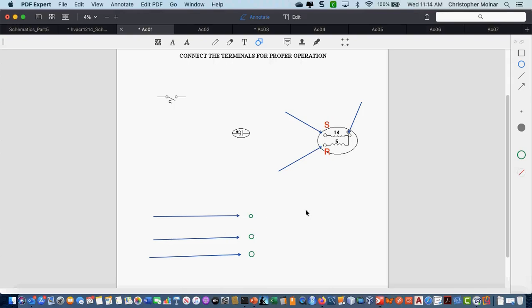You're going to take a resistance reading, let's say between the first two. Your resistance reading could be a 14. Then you're going to take a resistance reading between the second two. Let's say your resistance reading at that point is a 19. Then you have one more reading to take because you still have your third combination. I'm going to take a resistance reading between my two outer ones. So now I have a resistance reading of 5.